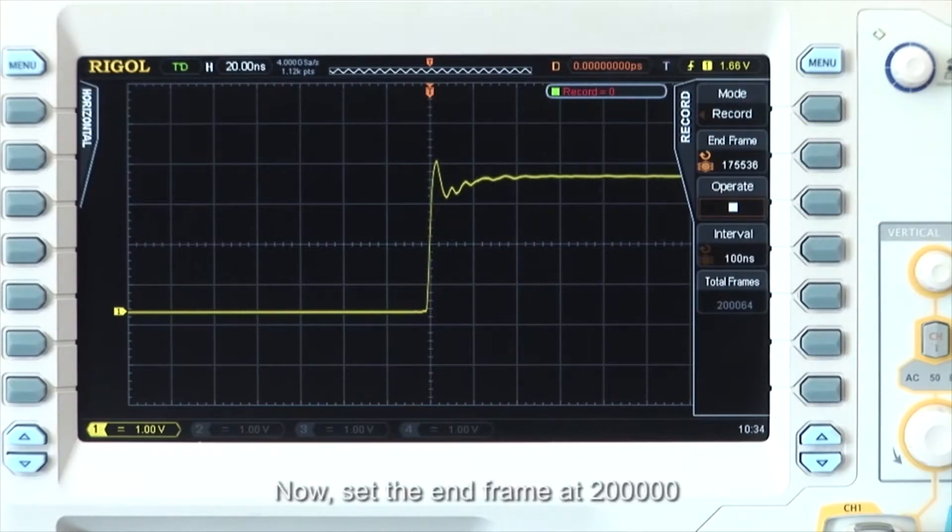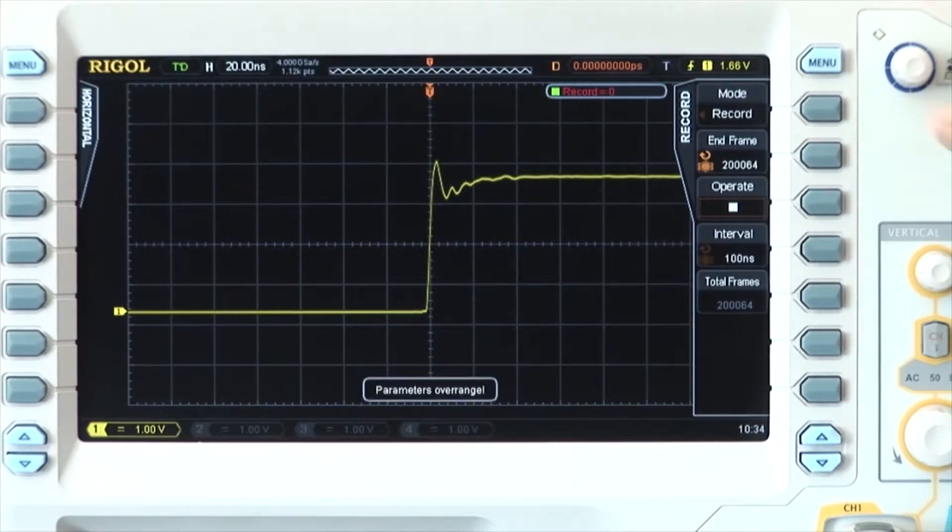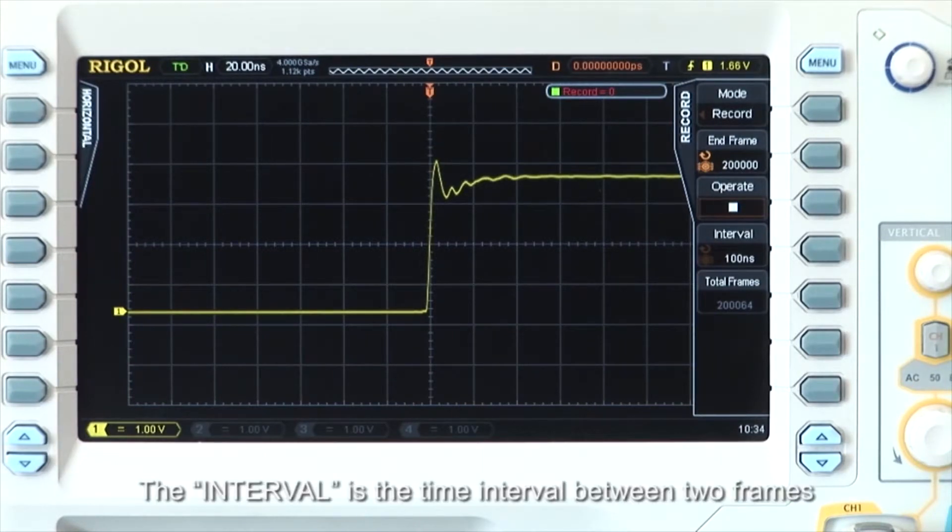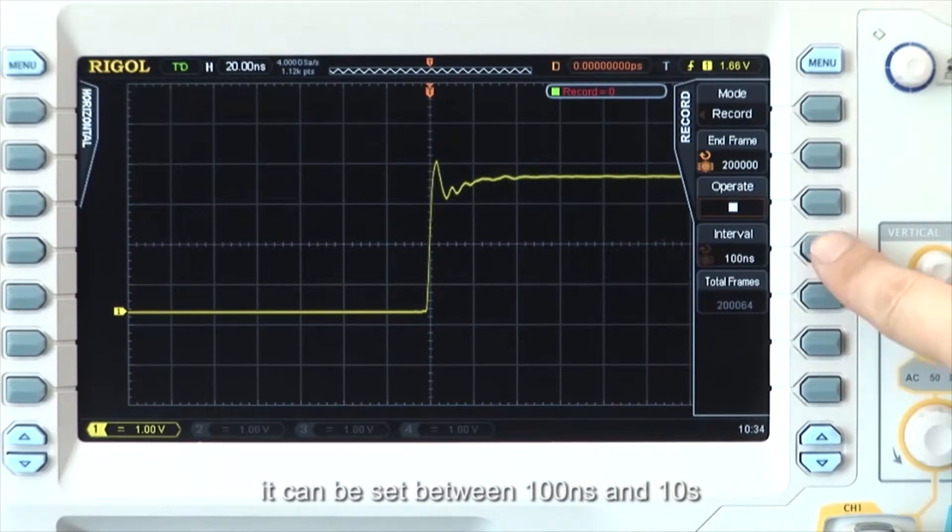Now set the end frame to 200,000. The interval is the time interval between two frames. It can be set between 100 ns and 10 seconds.